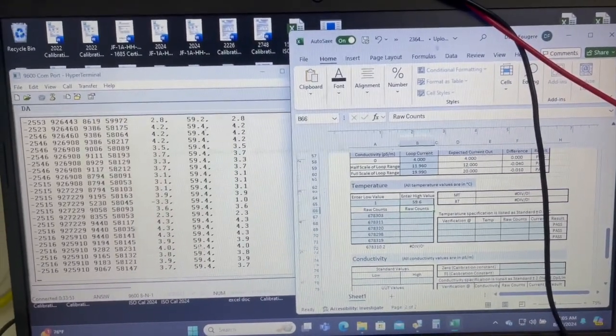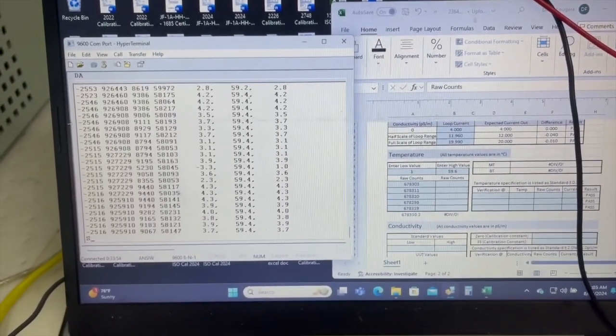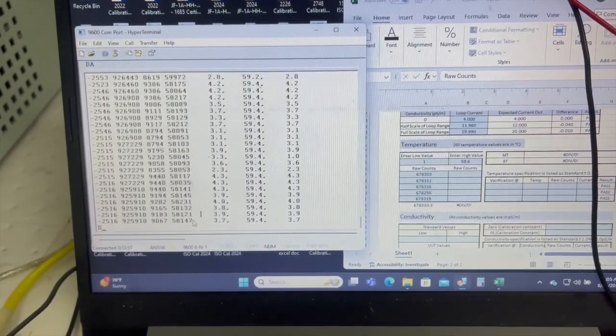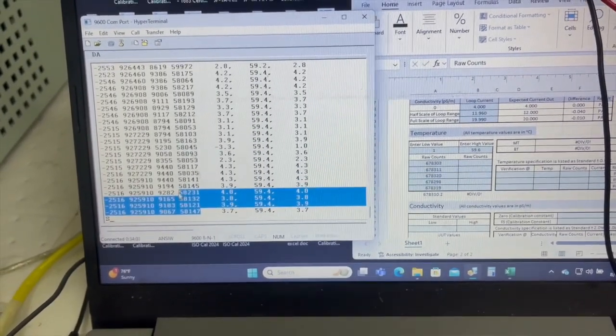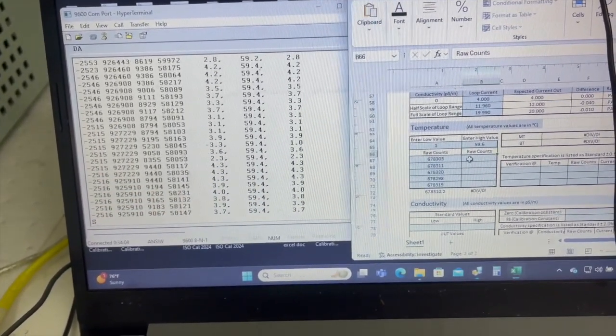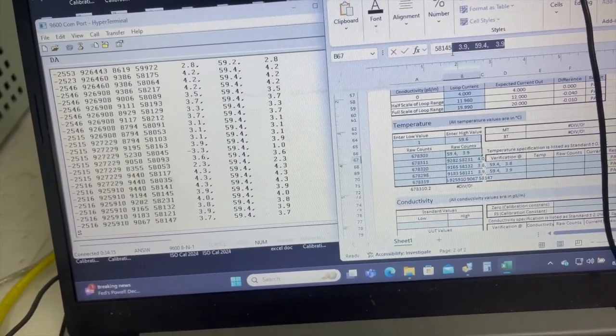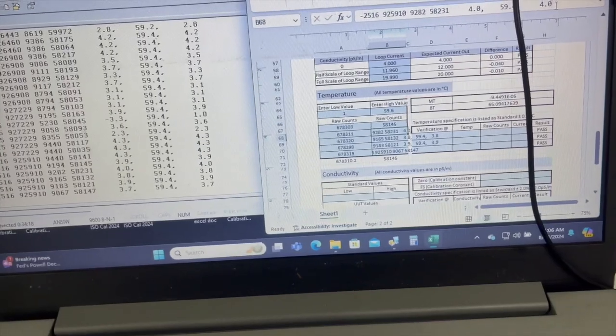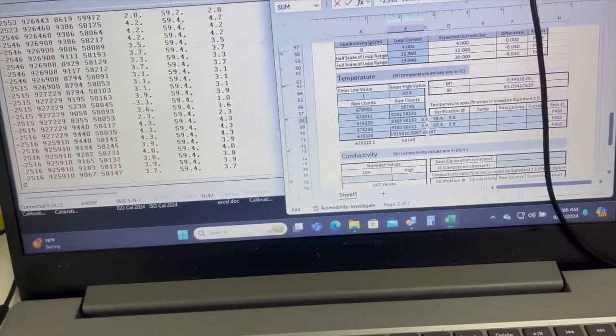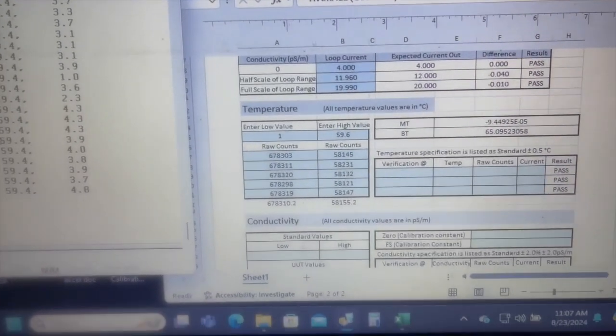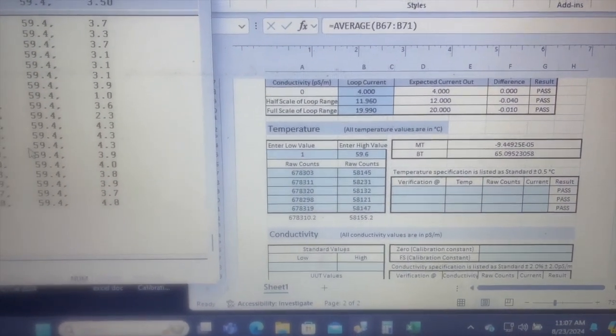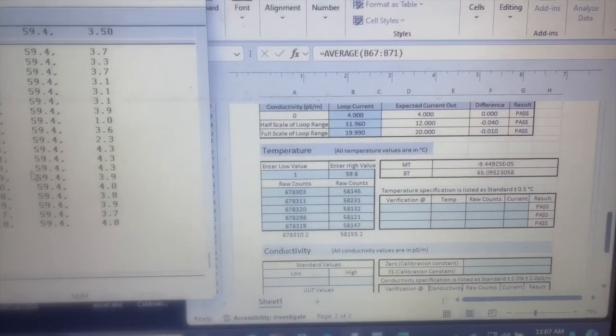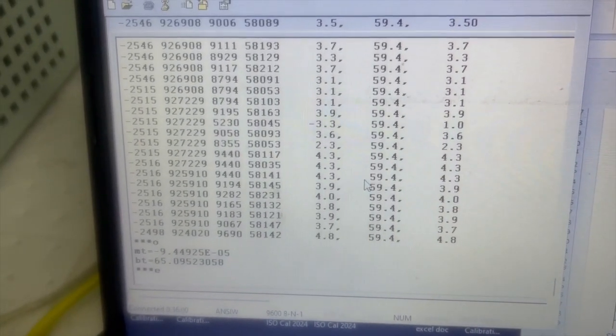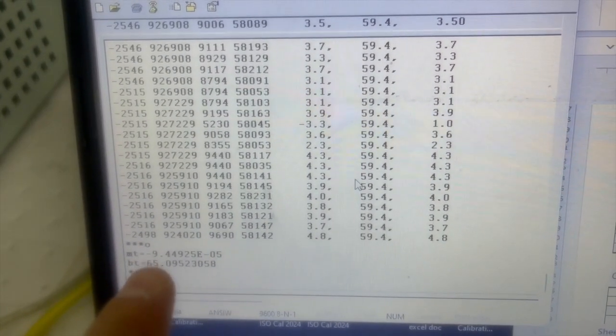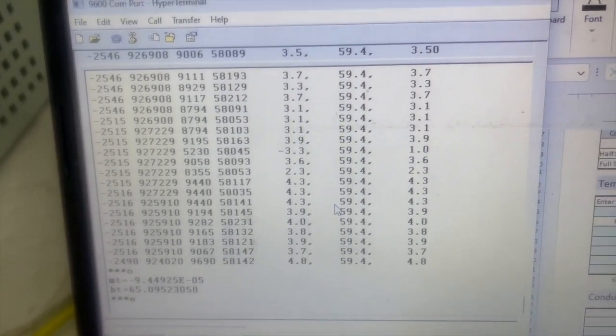you go over here and you'll write 59.60 in there, and then you'll go over here and you will grab the counts from this category here, which is the temperature counts. You'll copy those over, paste them in there, and get rid of the extra digits to get your MT and BT values, which you'll then plug into the sensor. Okay, so once you have your constants written into the sheet, it will help you with the math that we've already done for you, and it'll pump out an MT and a BT value that you're going to then put the sensor into open mode, star O, and then you're going to type out the MT and the BT value, and then you're going to save it into the sensor.